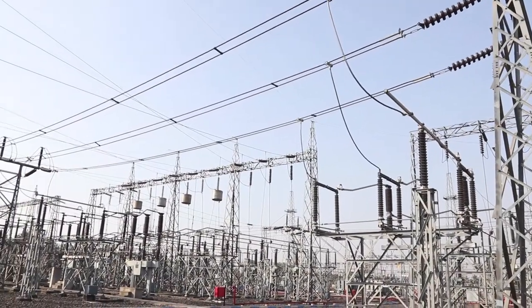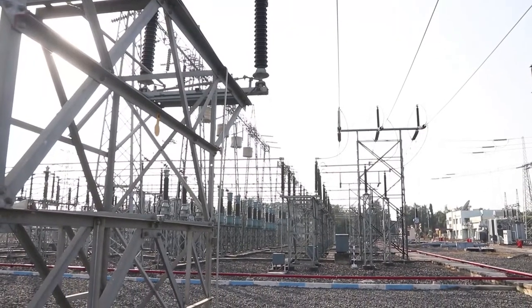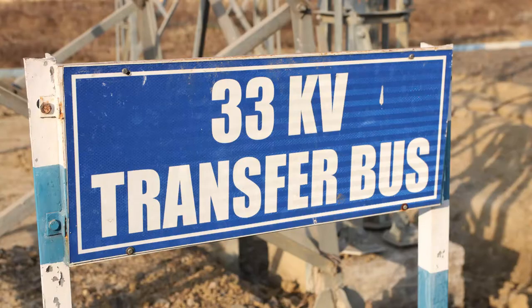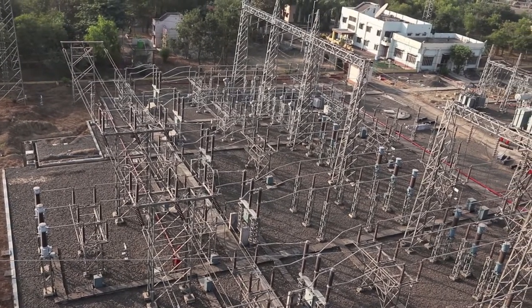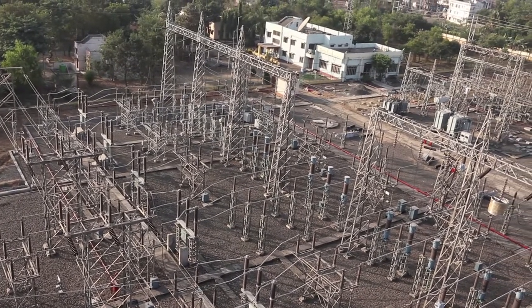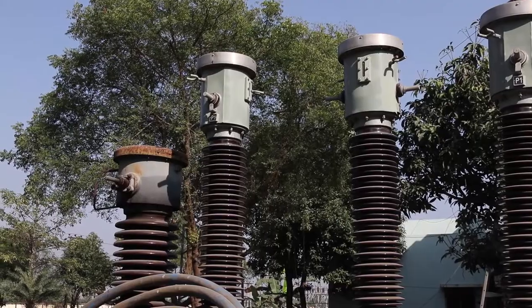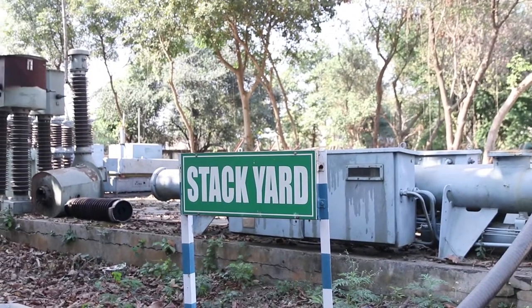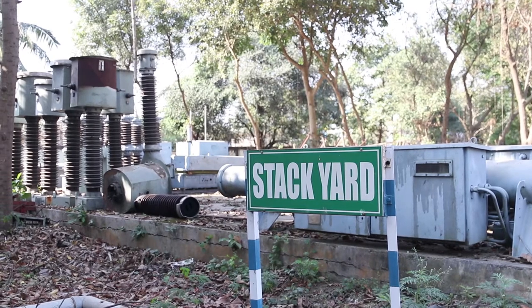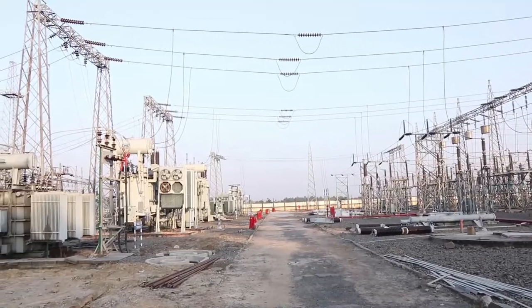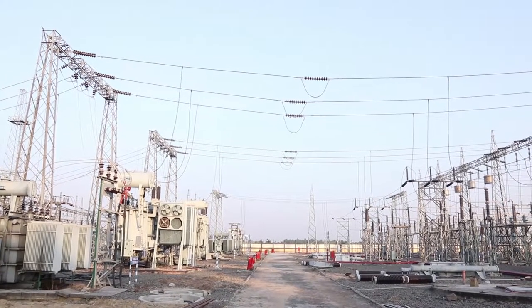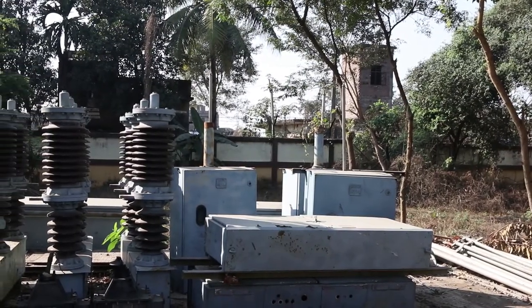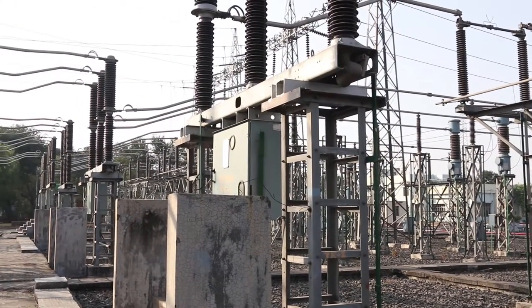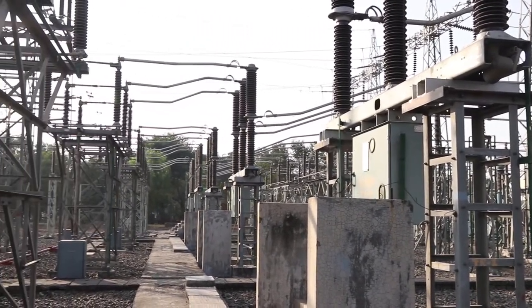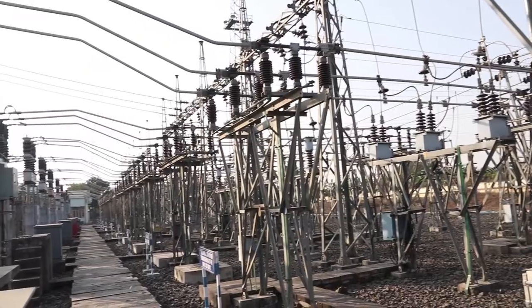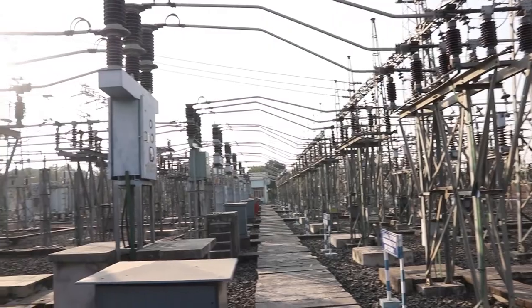This substation has main and transfer bus bar scheme at 132 kV and 33 kV system. This substation is almost 20 years old and old equipments have crossed their natural life. As a result, old equipments are being phased out. All old generation 132 kV SF6 hydraulic circuit breakers and 33 kV VCBs are already replaced by new generation 132 kV SF6 circuit breakers and 33 kV vacuum circuit breakers respectively.